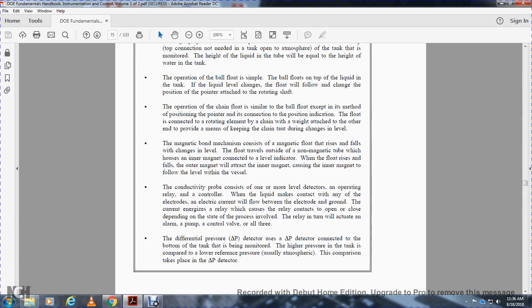The magnetic bond mechanism uses a magnetic float that rises and falls with the level. The float travels outside a non-magnetic tube, with the inner magnet connected to the level indicator. As the float rises and falls, the outer magnet will attract the inner magnet, causing the inner magnet to follow the float within the vessel.